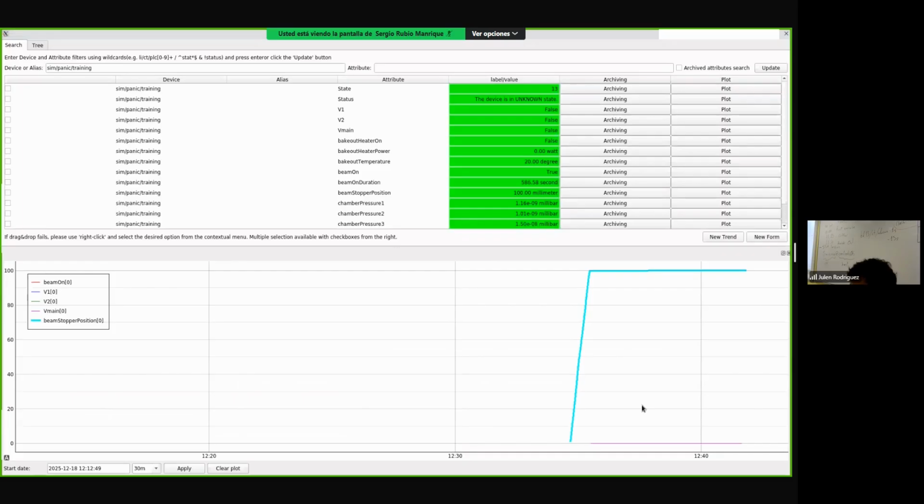and this is why our beamline EPS protection closes the valves. But our motor is still at 100, so this is why the alarm was active. This is a little bit of what happened and how to diagnose this alarm.